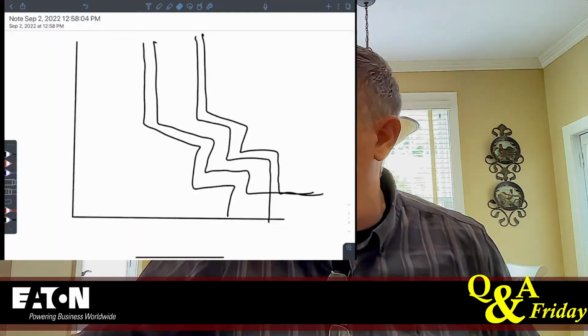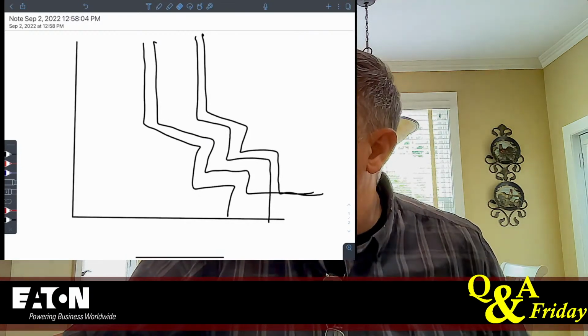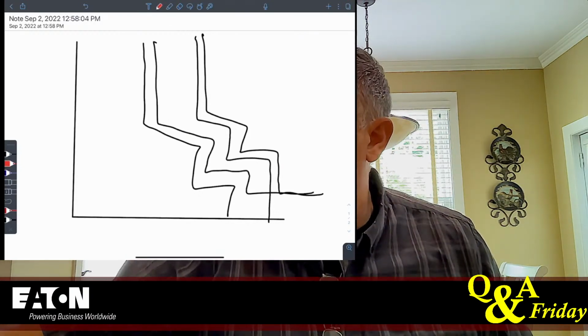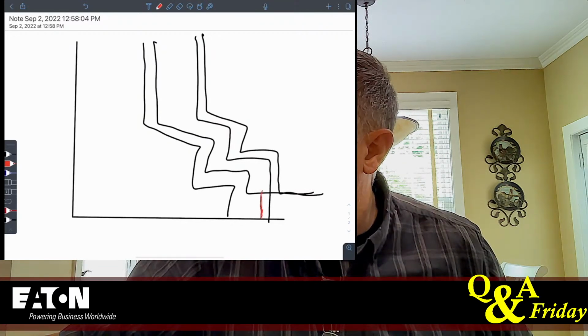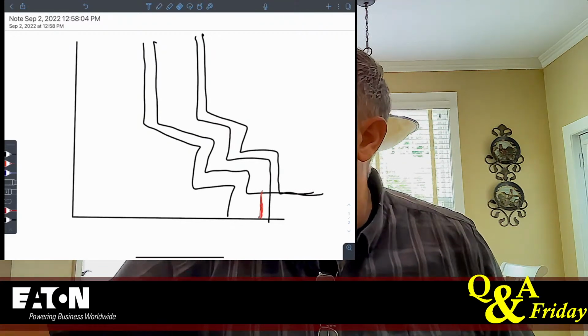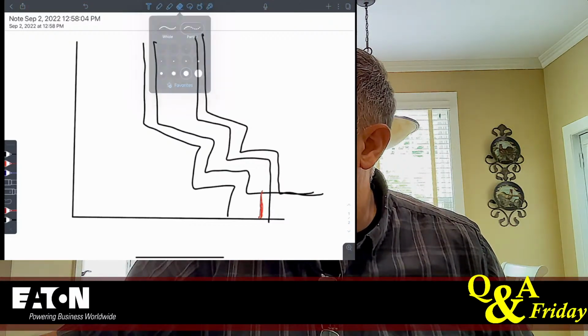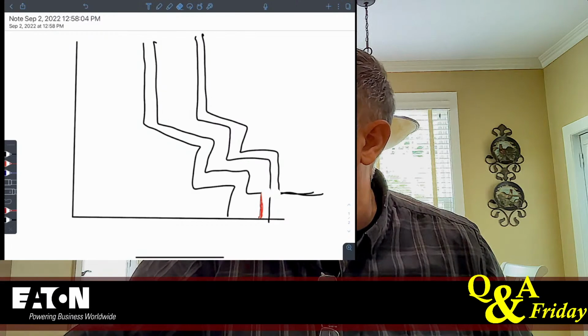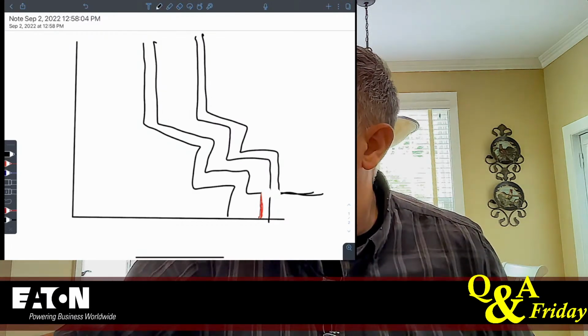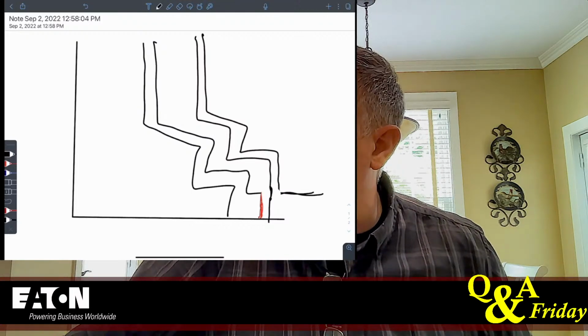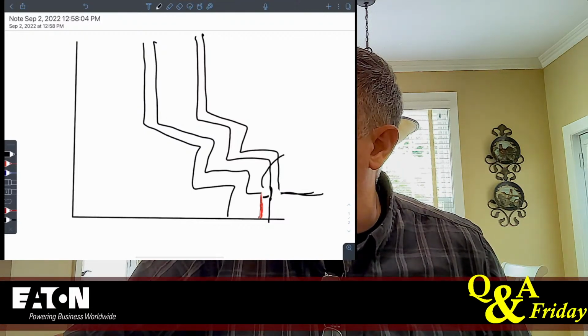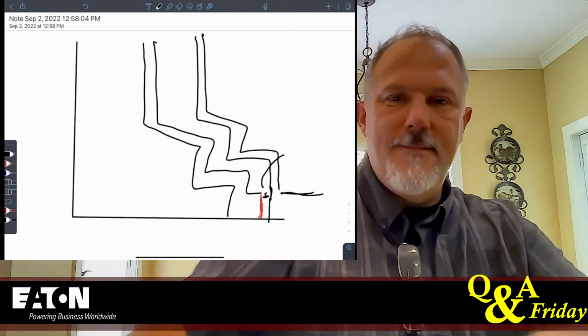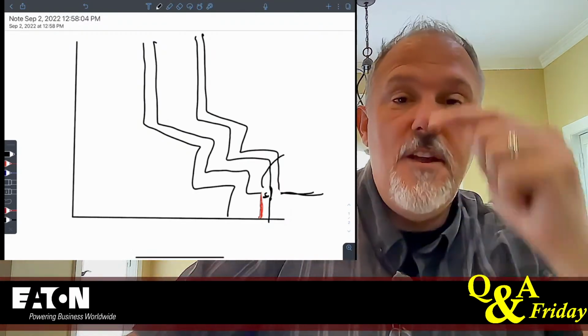Only if the fault current is less than the upstream breaker. And if it's less than the upstream, for example, if your fault current is here, okay, and let's say it cuts off the downstream breaker like that, right? So let's say that your downstream breaker is cut off and there's a space in between those two.